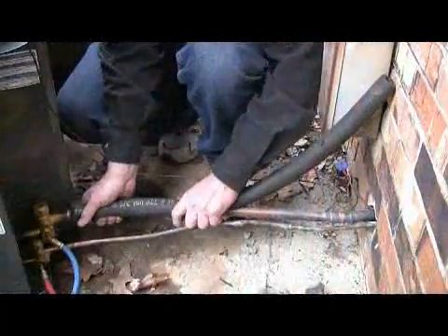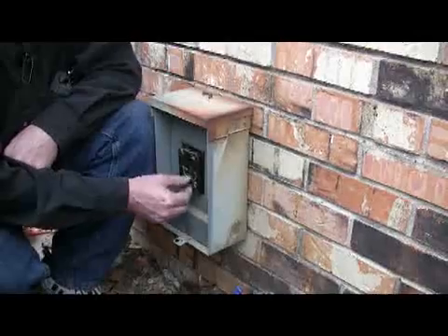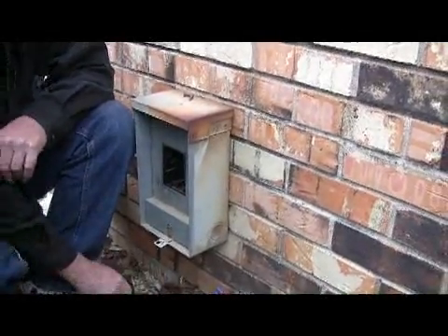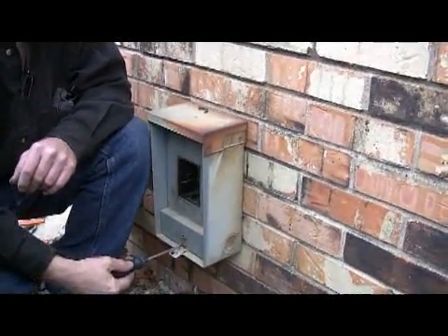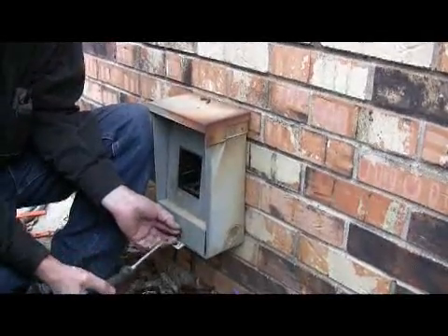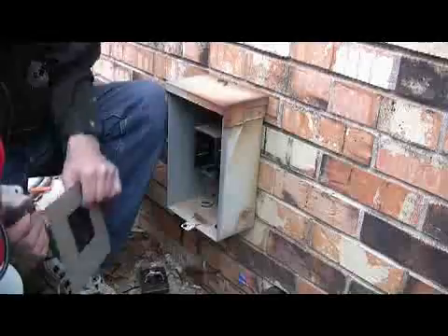That's actually for sweating purposes, all it's for. I'm going to use the old pull-out — it's in good shape, I didn't find anything wrong when I checked it before. But the seal tight going to the other unit was in poor shape. If I had found a problem with this and didn't trust the electrical integrity of it, I would have changed it.